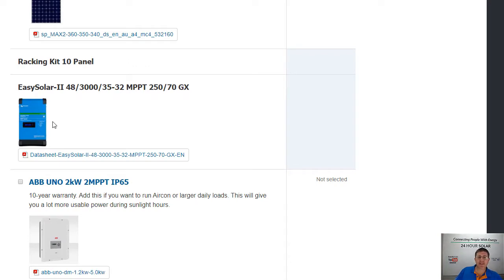Think about a 3 kVA inverter like this. Take a kettle and a toaster - a kettle pulls about 2,000 watts, and a toaster is somewhere between 1,000 and 1,500, let's say 1,500 watts. So you've got a 3,000 watt inverter, your 2,000 watt kettle on, then you flick the toaster on - you're going to have a blackout. That's what this means: you can only pull 3,000 watts total at the same time, and you don't want to be pushing these things to the limit.